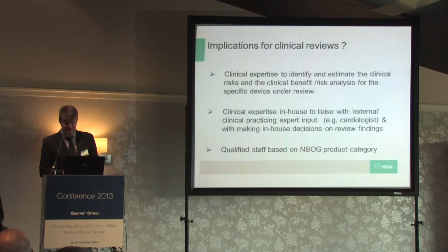With regard to studies, again I'm talking from the clinical side, this is my area, the expectation would be that the regulation would seek a clear understanding and scrutinisation of the appropriate design of the study. Not just the first-in-man, pilot or pivotal, there should be clear justification for the appropriate size and study design. There should be a clear, robust statistical justification for the sample size. This is something our competent authority is very strong on. Sample size justification for these high-risk devices is very important. So we're trying to demonstrate safety and performance, so the claims being made need to substantiate the appropriate sample size.